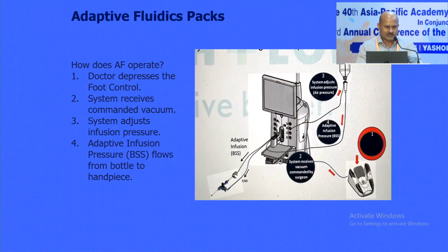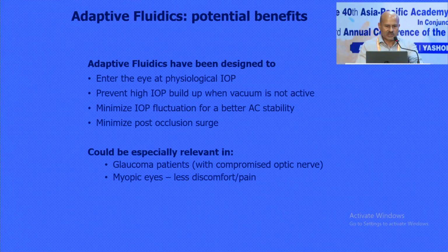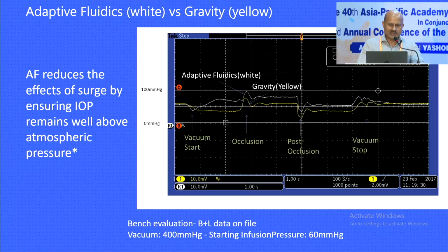So this is the whole setup. The doctor depresses the foot control, the system receives the command, the vacuum is sensed, the system adjusts the infusion pressure, and adaptive infusion pressure flows from the bottle to the handpiece. So the chamber is very stable. These are the parts of it. So the potential benefit is again surgery at physiological IOP, good for glaucoma patients and high myopia. So this is again gravity driven in their own diagram, showing that it is better surge control than gravity driven infusion.